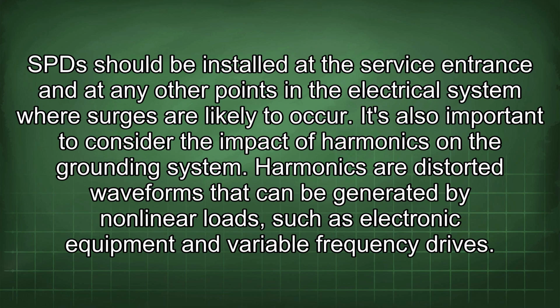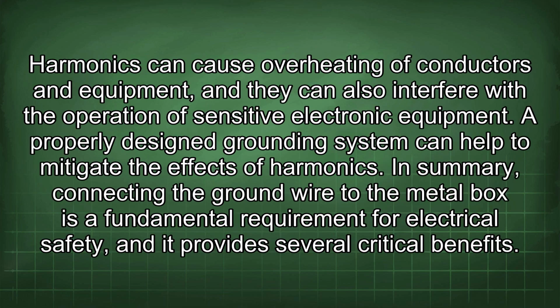It's also important to consider the impact of harmonics on the grounding system. Harmonics are distorted waveforms that can be generated by nonlinear loads, such as electronic equipment and variable frequency drives. Harmonics can cause overheating of conductors and equipment, and they can also interfere with the operation of sensitive electronic equipment. A properly designed grounding system can help to mitigate the effects of harmonics.